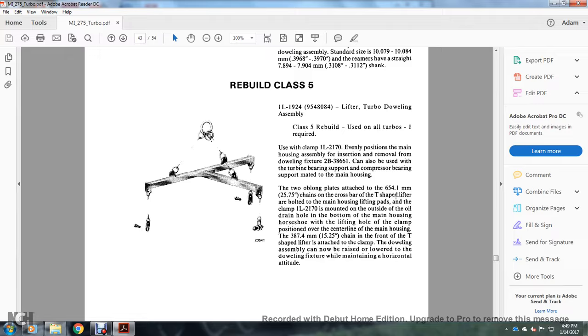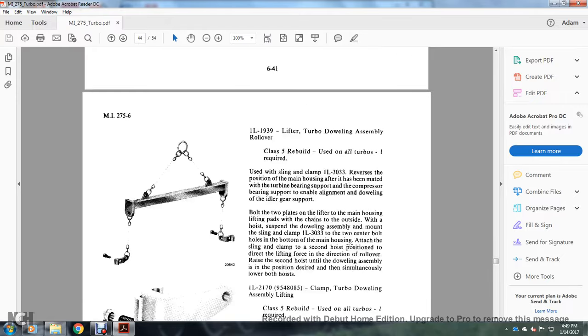The chains have crossbars. The T-shaped lifter holder is bolted to the main housing lifting pad. The clamp is mounted on the outside of the oil drain hole in the bottom of the main housing horseshoe, with the lifting hole of the clamp positioned over the center line of the main housing at 387.4 millimeters or 15 1/4 inches. The front of the T-shaped lifter shall be attached to the clamp. The dowelling assembly can now be raised and lowered into the dowelling fixture, maintaining a horizontal attitude.